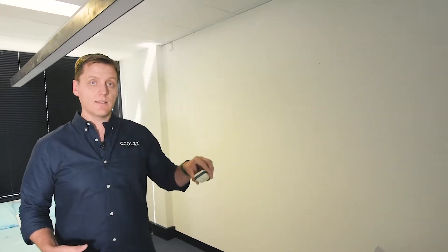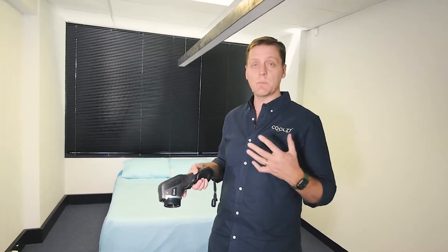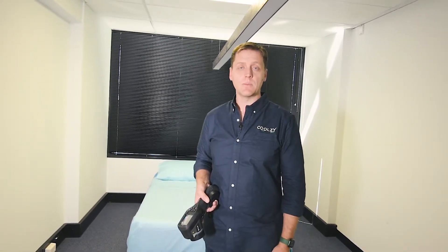We'll set up the sound meter at 1.2 meters from the unit. That's about 56 and a half decibels. For those of you that know anything about sound energy, for every three decibels you go up the noise roughly doubles. It's noticeably louder in here — I can feel that I have to speak louder to hold a conversation. If there was a second person here we'd have to speak quite loudly to be able to talk.